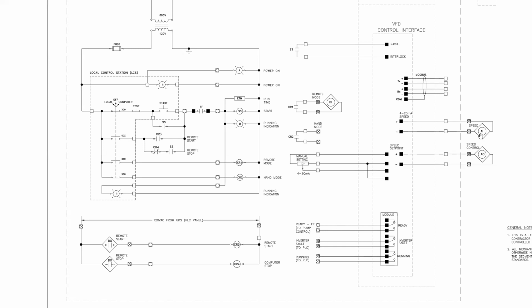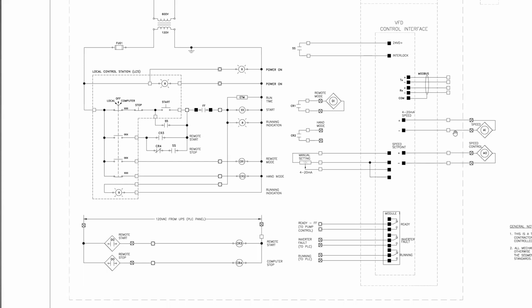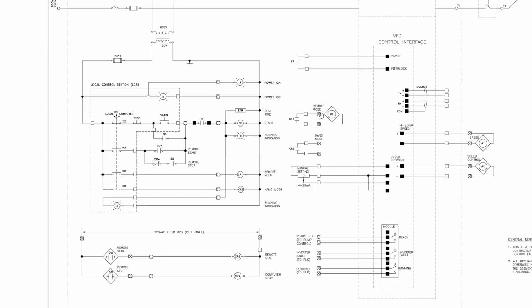Here we have an AI, so there's going to be an analog input from the PLC to indicate how fast the pump is going, and the speed set point is an AO. So this is indicating that there's an analog output from the PLC that's going to set the speed of this pump, and an input that's going to read the pump back. Down here, again, when it's in local, we have CR2. So when this is true, that CR2 coil will pull in, and this is hand mode. So again, this is an indication that this is going to be wired to a PLC. If we were to go back to the legend and find this circle with an X, we'd probably find that that is an indication of an IO point of some sort.